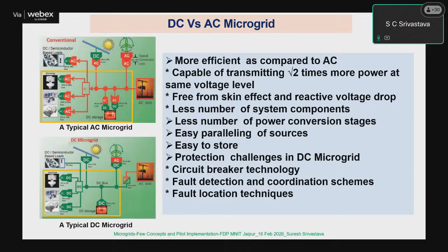So why does it become difficult? If you see AC, there is a sustained oscillation, and slowly the fault stabilizes at some higher value. Whereas on the DC side, it reaches a very high peak very fast. And in microseconds, it dies down and reaches a very low value, comparable to your load current or maybe 1.5 times load current. So in steady state, it is difficult to distinguish. But your protection has to operate in microseconds. That is the difficulty we have because of the DC coupling voltage. This peak comes. So that is how protection in a DC network becomes very challenging.